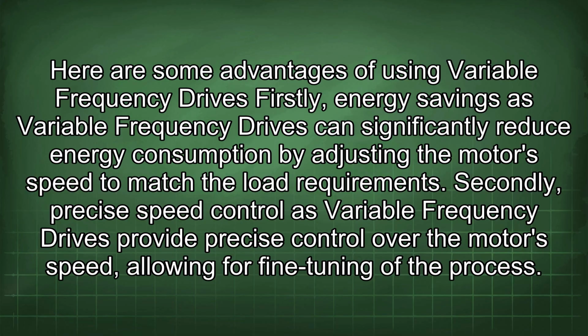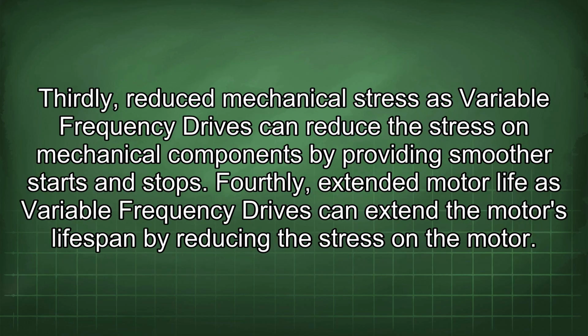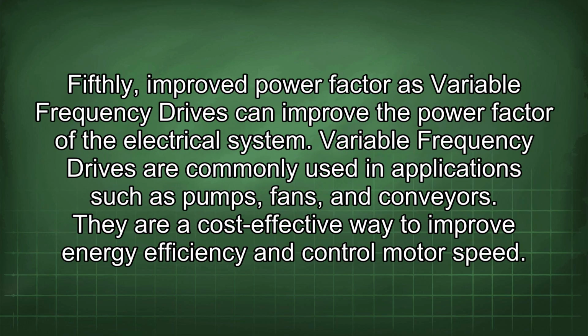Secondly, precise speed control, as variable frequency drives provide precise control over the motor's speed, allowing for fine-tuning of the process. Thirdly, reduced mechanical stress, as variable frequency drives can reduce the stress on mechanical components by providing smoother starts and stops. Fourthly, extended motor life, as variable frequency drives can extend the motor's lifespan by reducing the stress on the motor. Fifthly, improved power factor, as variable frequency drives can improve the power factor of the electrical system. Variable frequency drives are commonly used in applications such as pumps, fans, and conveyors. They are a cost-effective way to improve energy efficiency and control motor speed.